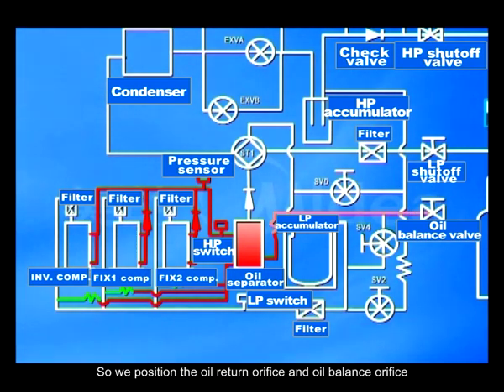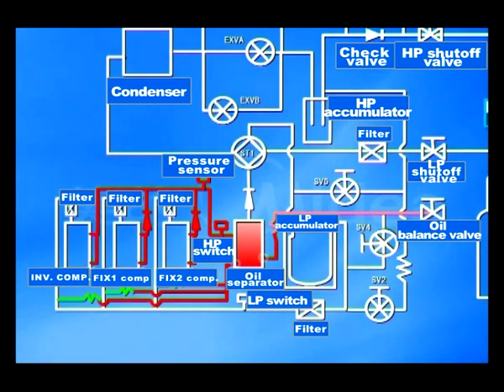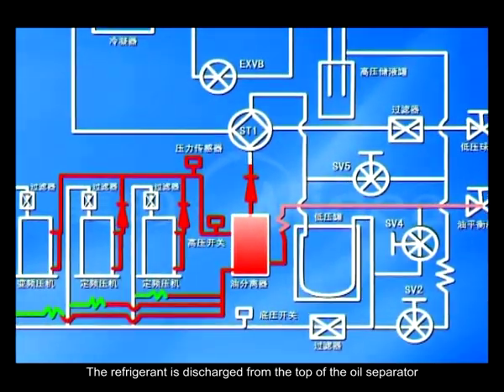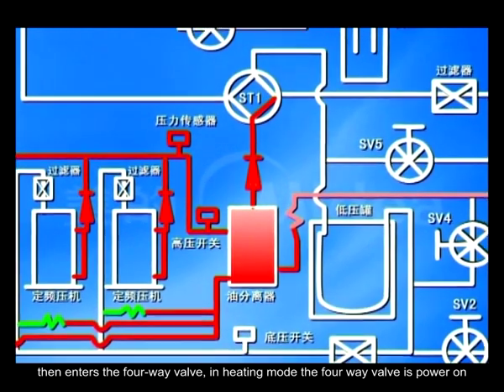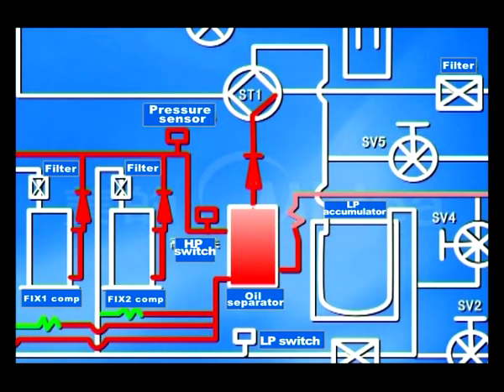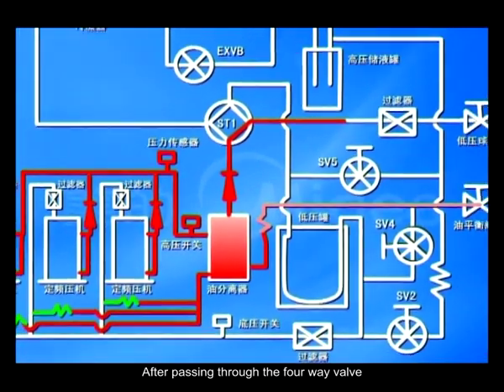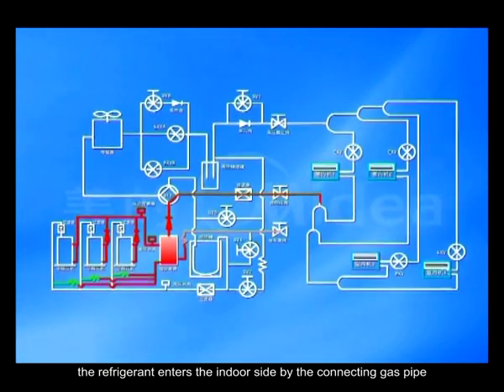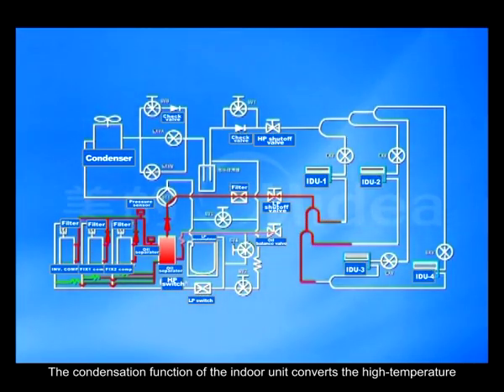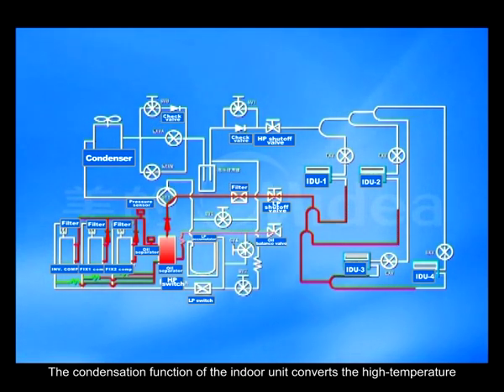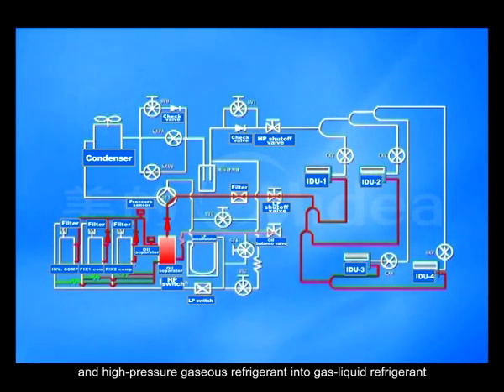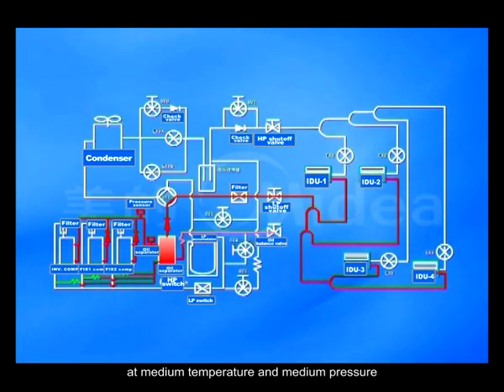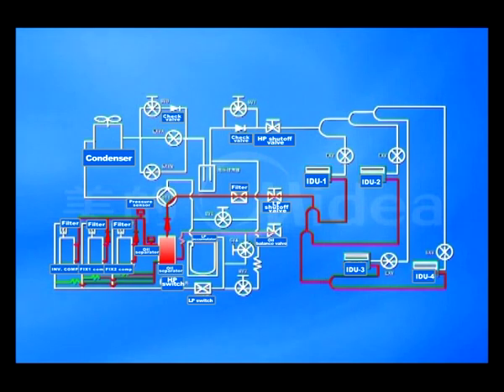So we position the oil return orifice and oil balance orifice at different levels at the bottom of the oil separator. The refrigerant is discharged from the top of the oil separator, then enters the four-way valve. In heating mode, the four-way valve is powered on. After passing through the four-way valve, the refrigerant enters the indoor side by the connecting gas pipe. The condensation function of the indoor unit converts the high-temperature and high-pressure gaseous refrigerant into gas-liquid refrigerant at medium temperature and medium pressure.